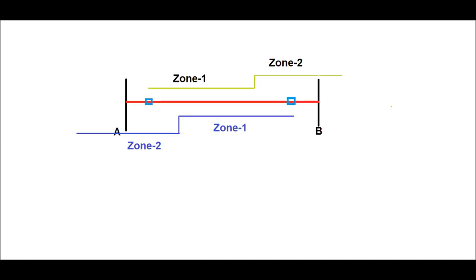Consider a line AB. Zone 1 is 80% of the line length protected by the relay at the A end, and zone 2 is the remaining 100% or 120% of the line length, as shown by the green line for relay A. Similarly, for relay B, zone 1 and zone 2 have been shown by the blue line.